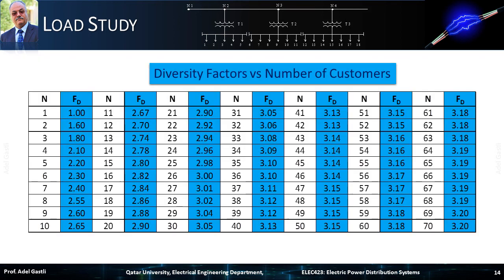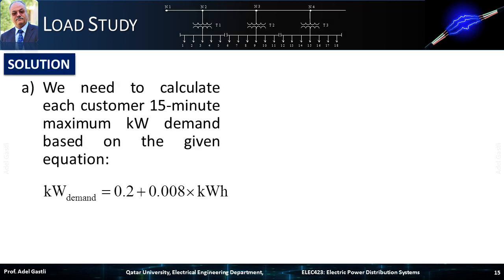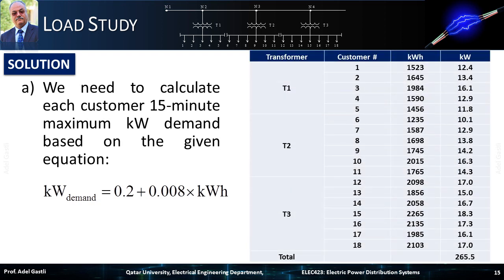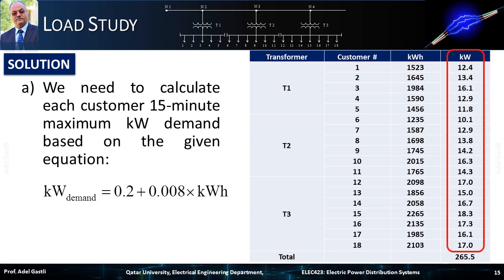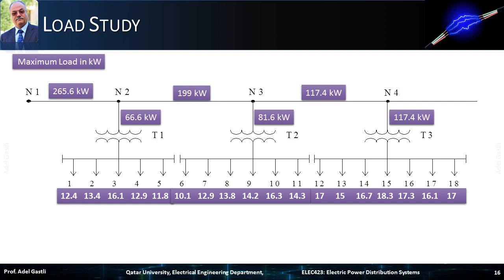This table provides the diversity factors versus the number of customers. To answer the first question, we need to calculate each customer's 15-minute maximum kilowatt demand based on the given equation. Thus the following table can be constructed. For instance, for customer 1 on transformer T1, the recorded energy consumption is 1523 kilowatt-hours, which according to the given equation gives a maximum demand of 12.4 kilowatts. Following the same procedure for all customers and using the given equation, the last column of the table can be easily constructed. To find the maximum demand on a transformer, we just sum the maximum demands of all consumers connected to the transformer. And for the feeders, we sum the maximum demands of the transformers fed by the feeder.